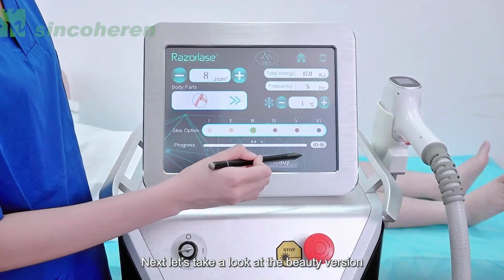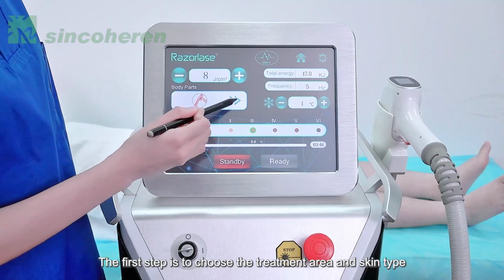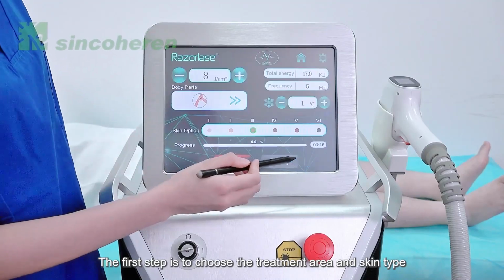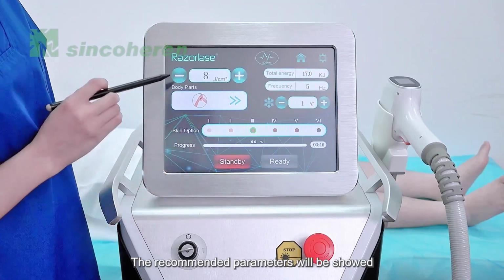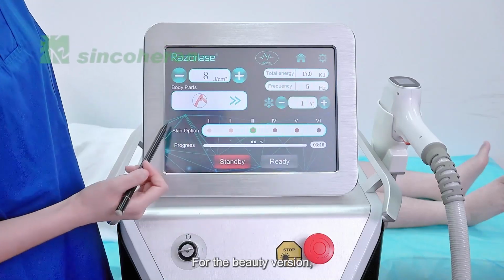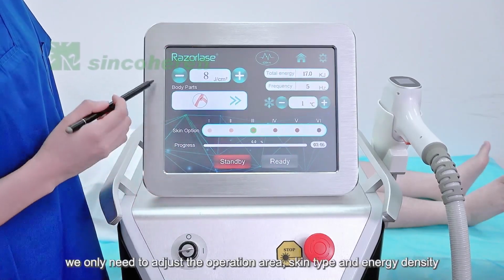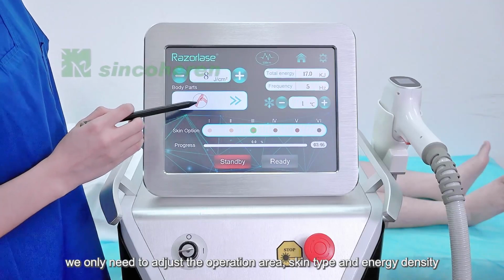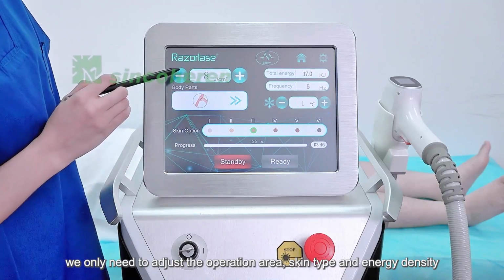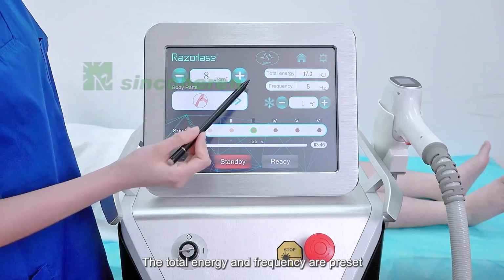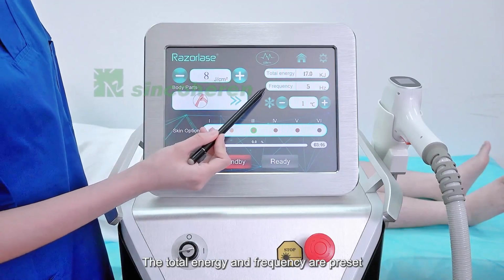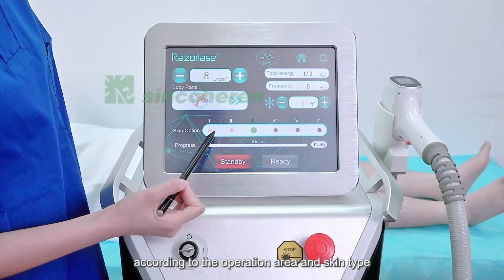Next, let's take a look at the beauty version. The first step is to choose the treatment area and skin type. The recommended parameters will be shown. For the beauty version, we only need to adjust the operation area, skin type and energy density. The total energy and frequency are preset, according to the operation area and skin type.